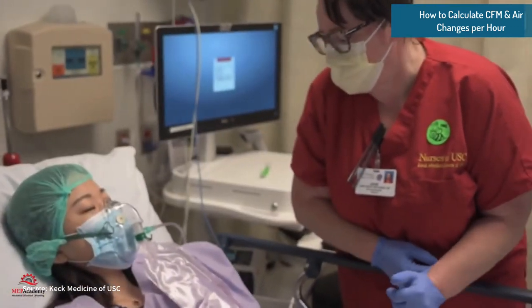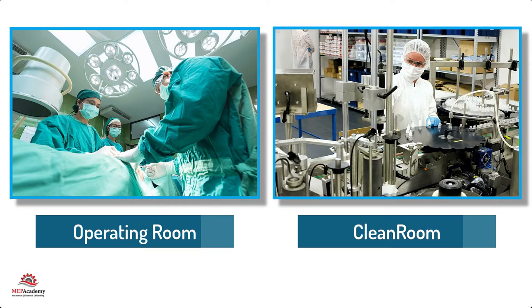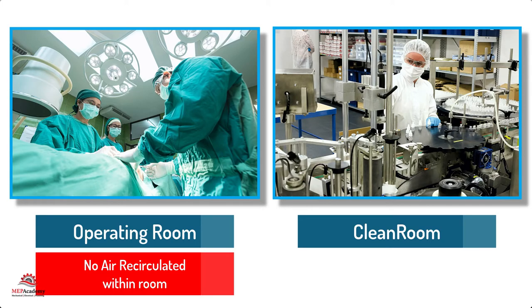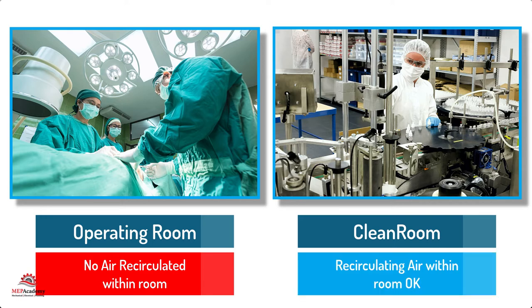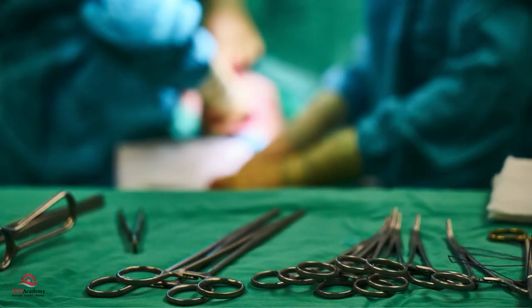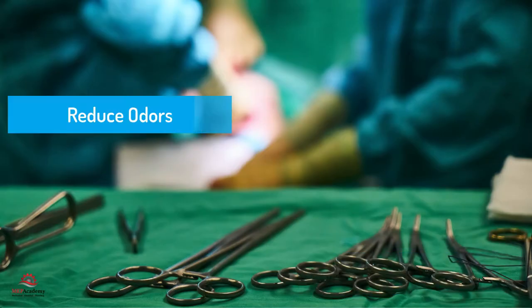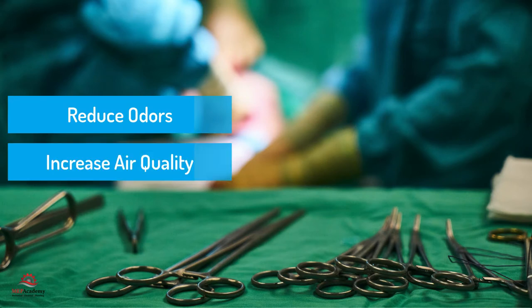The difference between a hospital room like an operating room and a clean room is that the operating room doesn't allow the air to be recirculated within the space, as opposed to a clean room where the use of fan-powered recirculation units are acceptable to achieve the required cleanliness level. Increased air changes reduce odors and increase air quality and cleanliness.